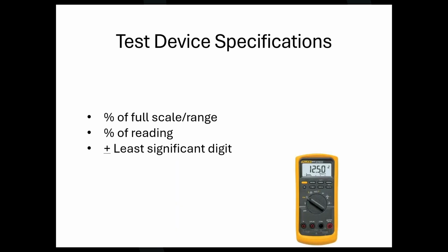What that is, is a plus or minus of your least significant digit. So if you're looking at this, and this multimeter, for example, says 12.50, and we had a 1 there, plus or minus 1, what would be our tolerance in this? It would be 0.01. So that last digit could be 0.51 or 0.49. So that is not a percentage typically like that. And that means you have to look, how many digits do I go out?